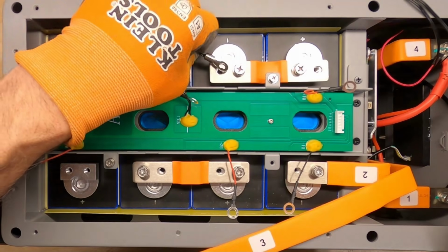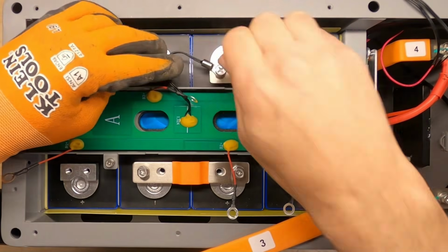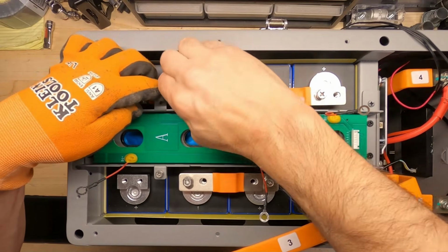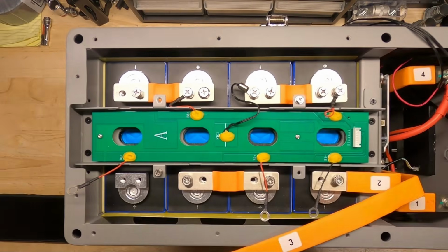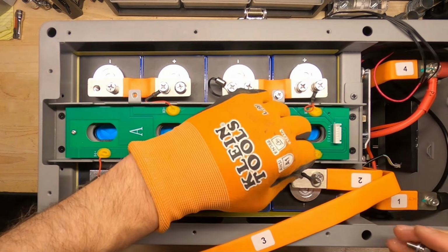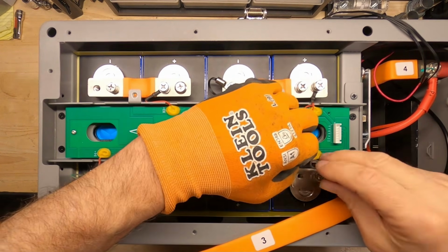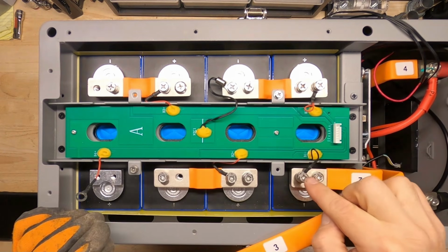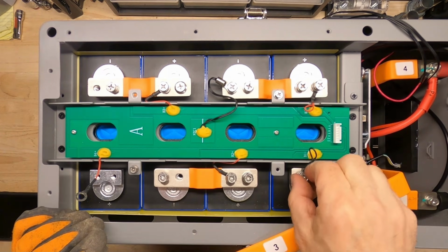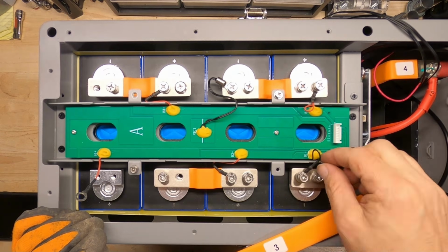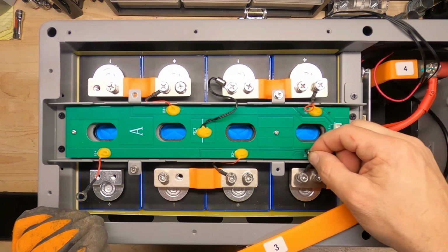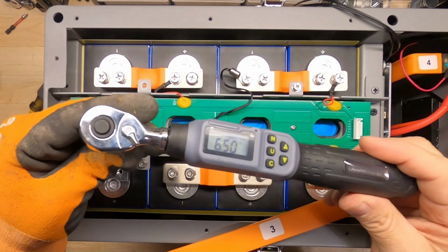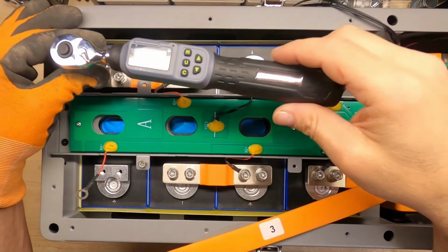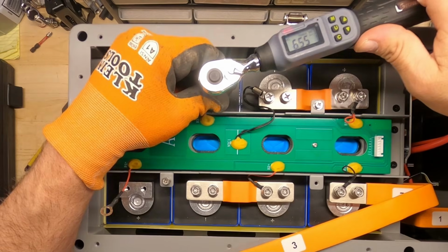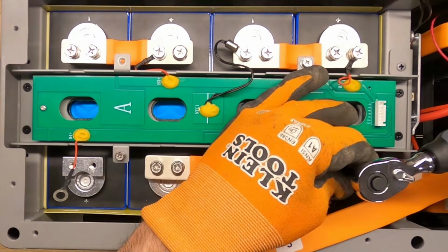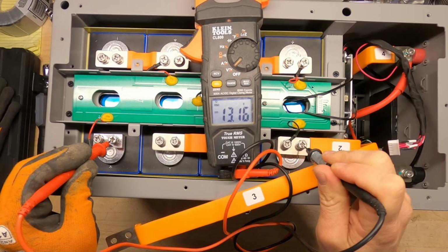So we'll do our temp sensor first. Our negative BMS lead. Now one thing that's nice about these screws with lock washer is when they tighten the balance leads, they will not rotate the balance lead. They'll stay there. 6.5 Newton meters. I like to go a little high. Should get about 13 volts. There we go, 13 volts. Perfect.